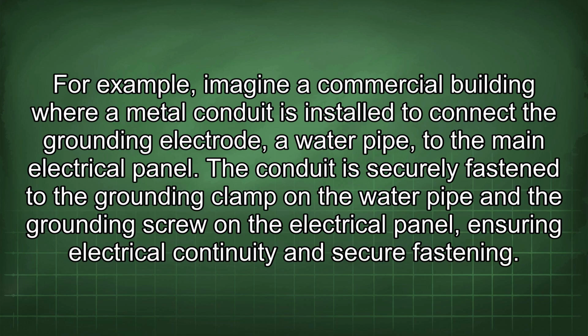For example, imagine a commercial building where a metal conduit is installed to connect the grounding electrode, a water pipe, to the main electrical panel. The conduit is securely fastened to the grounding clamp on the water pipe and the grounding screw on the electrical panel, ensuring electrical continuity and secure fastening.